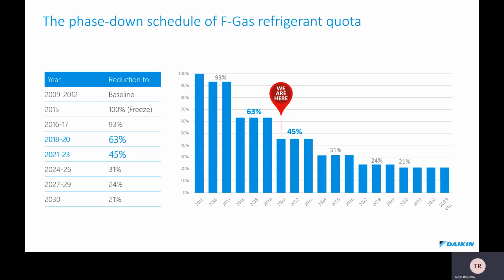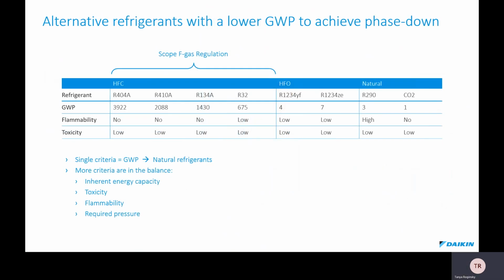This graph, I'm sure, is not new to you. It represents the phase-down steps of the F-gas refrigerant quota, and Daikin is contributing to it by driving the market to lower global warming potential alternatives. In terms of refrigerant alternatives, different types are being marketed. And global warming potential is not the only criterion for selecting a refrigerant. What about the refrigerant thermal capacity? What about its toxicity, flammability, operating pressures? There are many factors to consider. Daikin's choice of R32 refrigerant was made after careful consideration of all those factors.